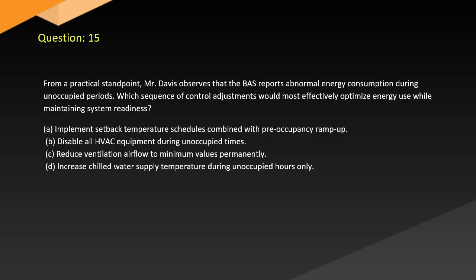Question 15. From a practical standpoint, Mr. Davis observes that the BAS reports abnormal energy consumption during unoccupied periods. Which sequence of control adjustments would most effectively optimize energy use while maintaining system readiness? A. Implement setback temperature schedules combined with pre-occupancy ramp-up. B. Disable all HVAC equipment during unoccupied times. C. Reduce ventilation airflow to minimum values permanently. D. Increase chilled water supply temperature during unoccupied hours only.